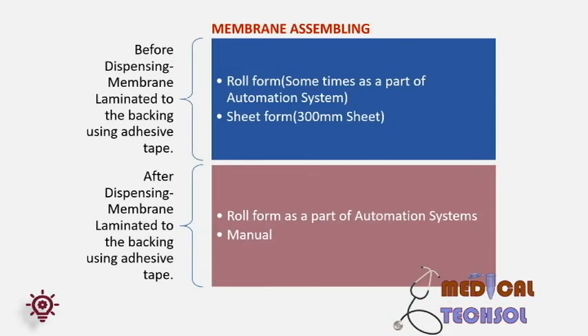Membrane assembling can be done in two different ways. First, before dispensing or coating: the membrane is laminated to the backing using adhesive tape, either by an automation system in roll form or in 300 mm sheet form. Second, after dispensing or coating: the coated membrane is laminated to the backing using an automation system, semi-automation, or manually by hand. Consistency will not be maintained in manual lamination. Sometimes a dedicated machine is used for lamination.